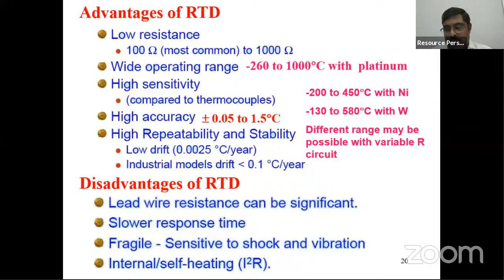The only thing is, in the case of the RTD, it's a very small, thin kind of film. It's very fragile in nature, so when you are handling it, you have to be very careful. And from this film we need to take the output, therefore we need to have a lead wire. Sometimes the lead wire will have some additional resistance that, of course, you need to account for. This can be done by proper calibration. These are all the issues associated with the RTD. But in general, for most R&D purposes, we use the RTD for temperature measurement anywhere between -200 and about 1000 degrees Celsius.